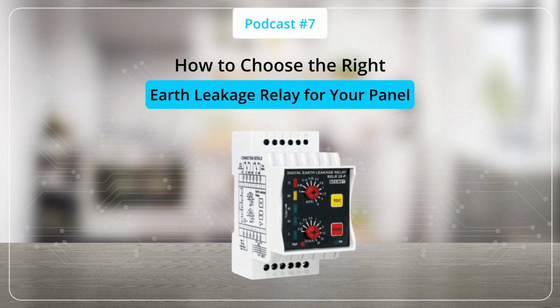Now let's go through a structured approach for selecting the right ELR. The first step is to study the load type. Determine whether the load is purely AC or contains DC components, such as those found in electric vehicle chargers or variable frequency drives. The second step is to define the protection objective. For personnel safety, 30 milliamps is generally recommended. For equipment and fire protection, settings between 100 and 500 milliamps may be more appropriate.